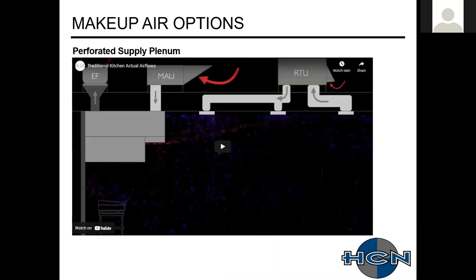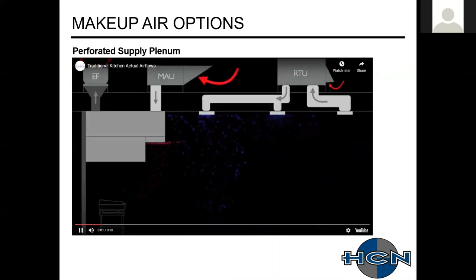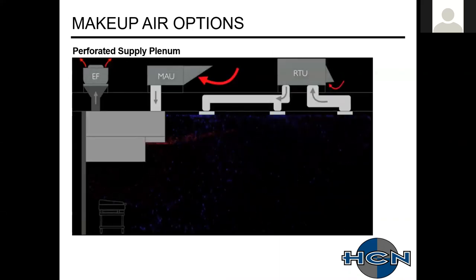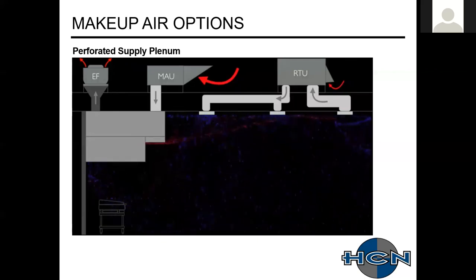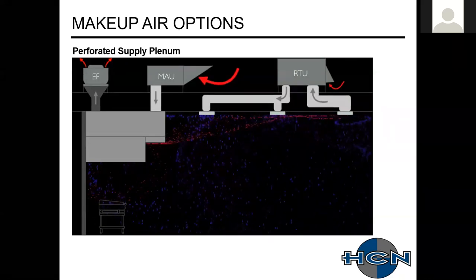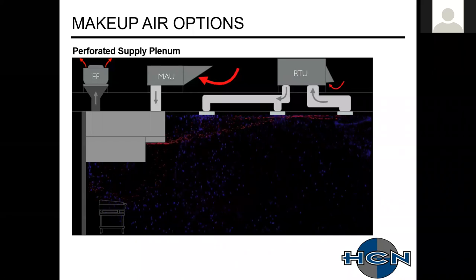Typically, this is what happens for most systems when they're not designed properly. Zach did another thing here showing the makeup air plenum not at the right velocity, where you're diffusing a lot of that makeup air into the space. This is just a heated only unit. So if this is the summertime, that hot humid air is getting pulled right into that rooftop unit. It's not going into the hood, not doing what you need the system to do, and all this cooler, nicer air is being sucked right back up into the hood system.